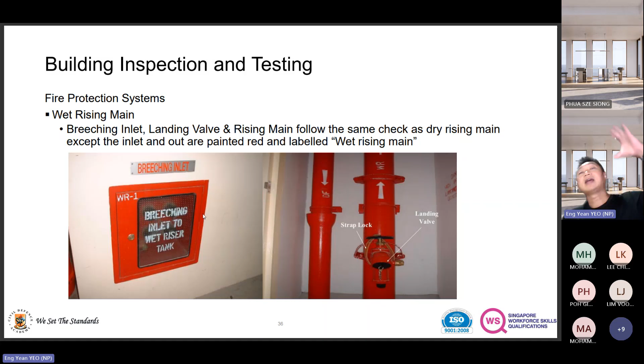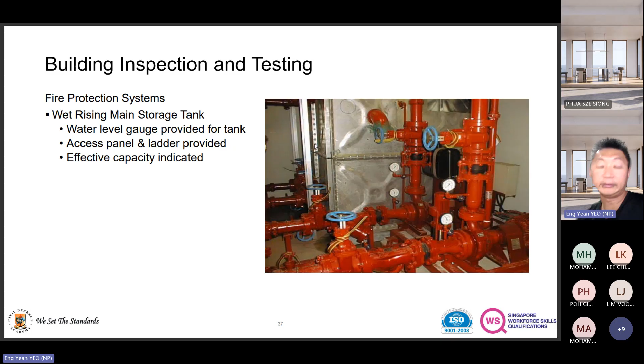Right, storage tank, usually there's some capacity over here. Look at the water meter, the water level, whether it is visible. If not visible, what I usually do, because it's a firefighting tank, so the water inside is not for consumption, is either put a color ping pong ball or styrofoam inside to make sure that you can see the level of water. So if the float valve gives way or is not operating at all, no one will know. There's a seepage, and only after a month we see a bill like, oh, how come it's 10,000, 20,000? So importantly, as PFM, I think we need to take the water and electricity consumption on a daily basis.